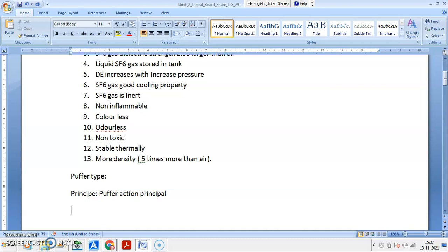So for the SF6 circuit breaker, SF6 gas is applied in the form of a blast, fast and quick. That is called puffer action, which is applied on the arc, so that arcing particles get swept away, the arc gets cooled, particles get decomposed in the arc extinction compartment and the arc gets extinguished.